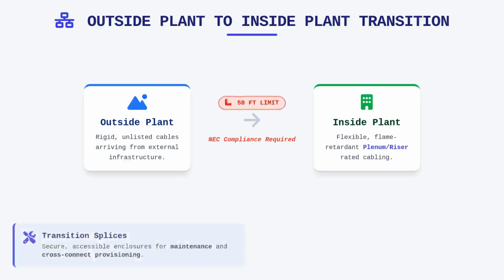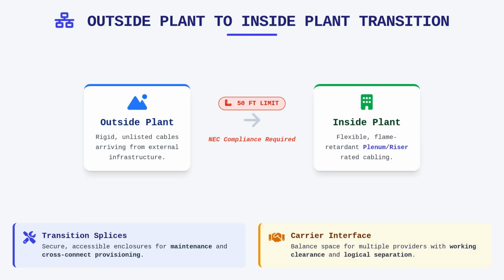You must plan for the necessary transition splices at or near the entrance location, ensuring they are contained within secure, accessible enclosures that allow for future maintenance and cross-connect provisioning. This location must also accommodate the specific space requirements of your carrier service providers, who will terminate their equipment and provide the initial demarcation for the building's connectivity. Designing for this interface requires balancing the physical space needs of multiple service providers while ensuring they each have adequate working clearance and logical separation for ease of daily operations.